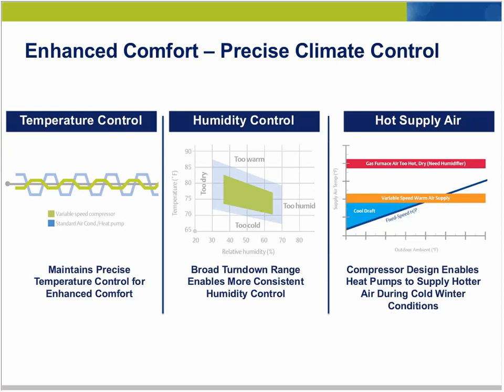Another benefit we sometimes see with modulation technologies, in particular heat pump applications, depending on how the unit is sized for the house, is that these technologies can deliver extra capacity when it gets cold, say down below 10 degrees ambient all the way to zero. It's like having two heat pumps in one. You get a lot more capacity for it, and that enables comfort with hotter heating air and more of it on those cold days.